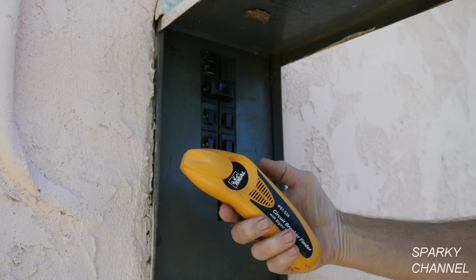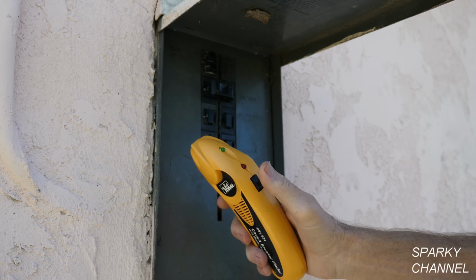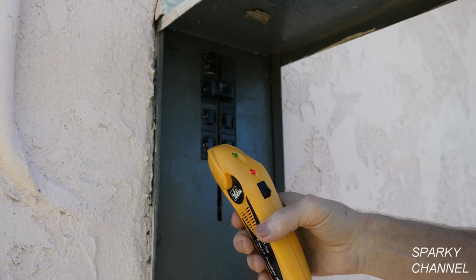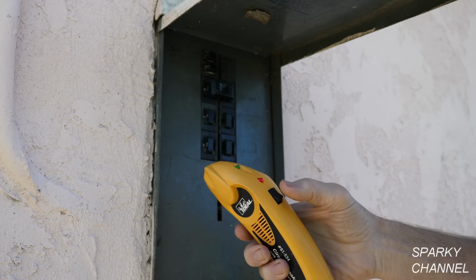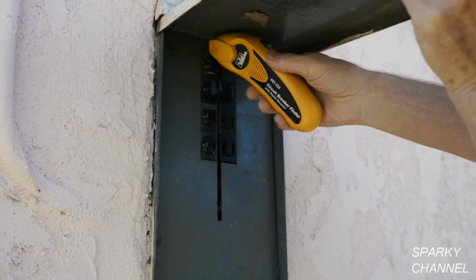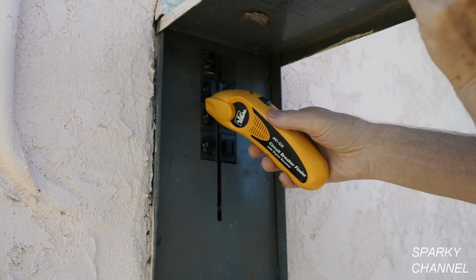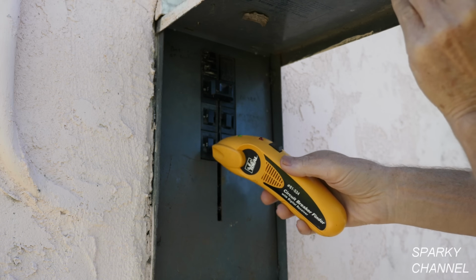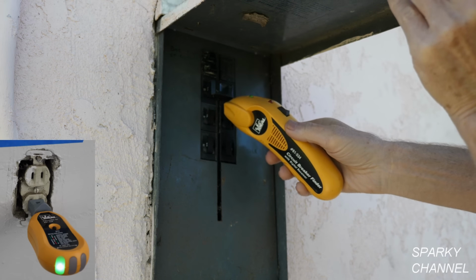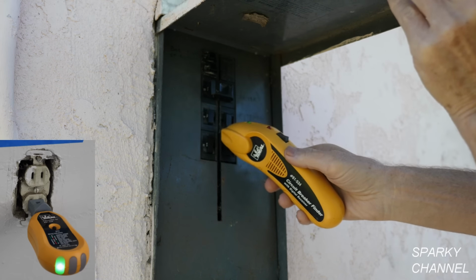All right, so this is the receiver. I'm at the main panel. Just take it, turn it on, and it chirps, and the green light and the red light are on. Now, go over all the breakers for relative strength. Do a good job of it. Okay, that indicates for the tester all the relative strengths. Okay, here's the receptacle. Here's the breaker right here. We push that and turn it off.